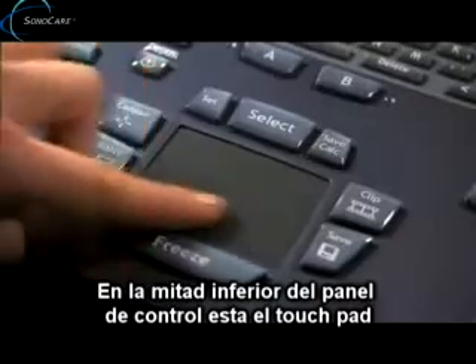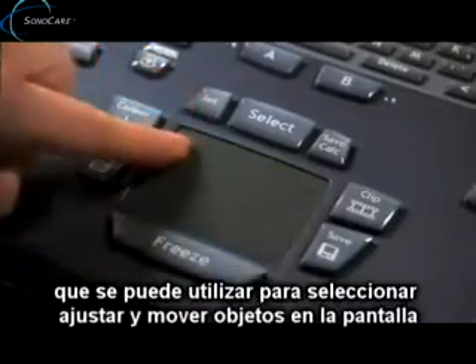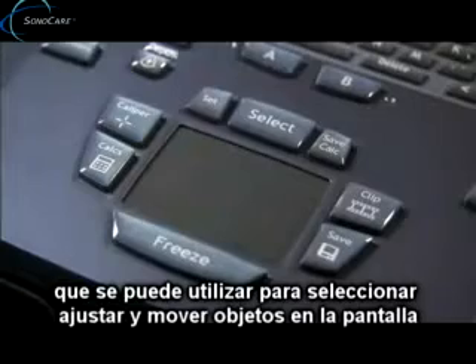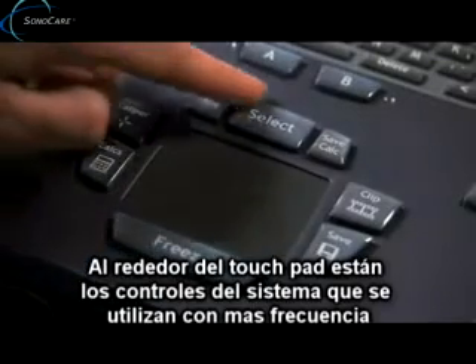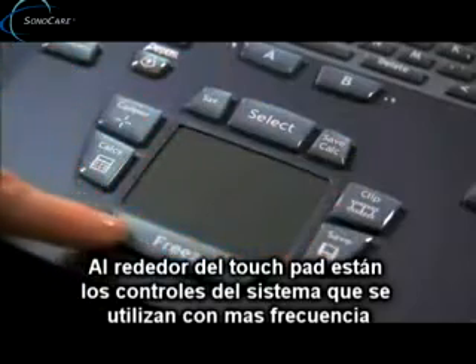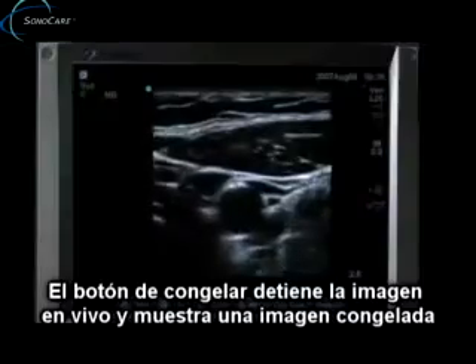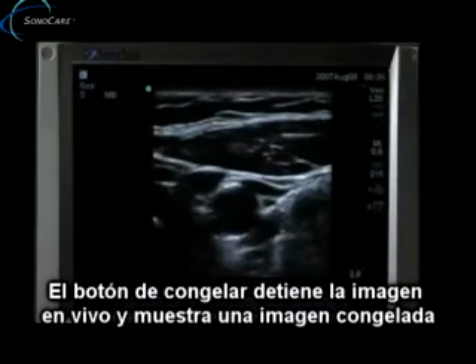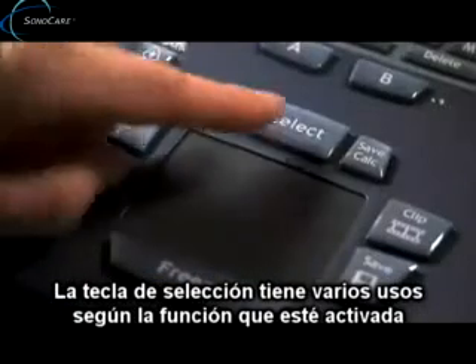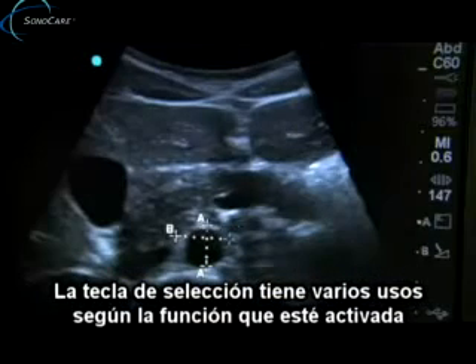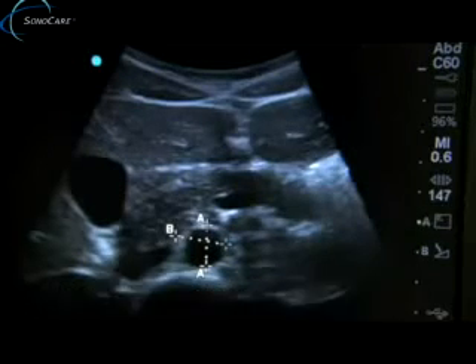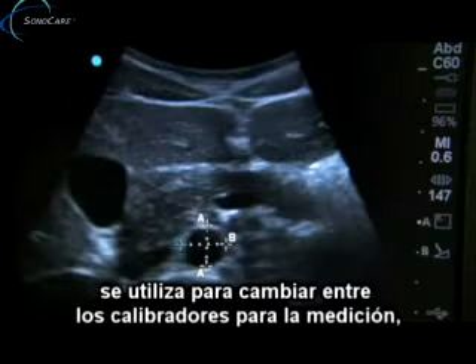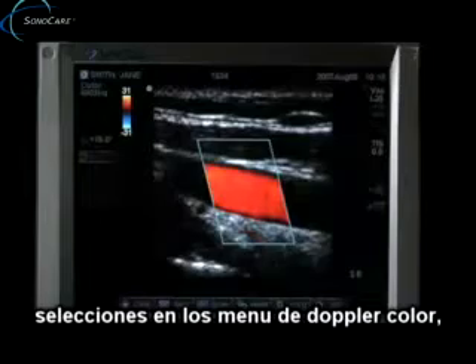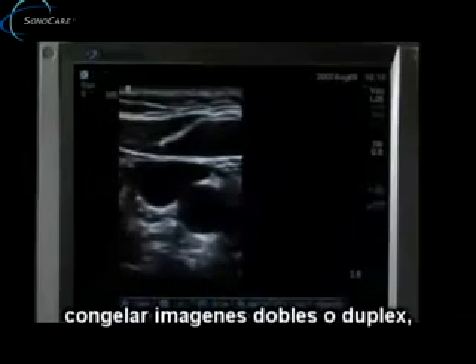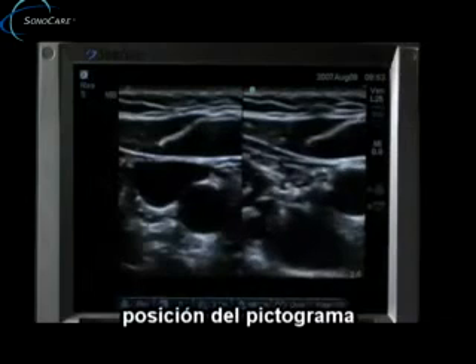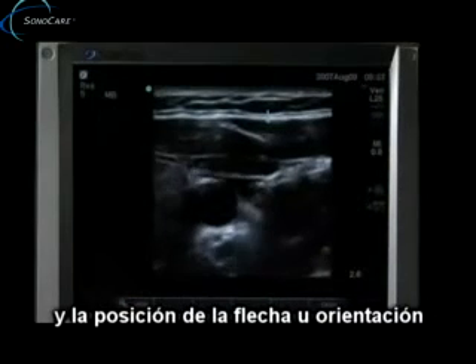In the lower middle of the control panel is the touchpad, which can be used to select, adjust, and move objects on the screen. Surrounding the touchpad are the system controls that are used most frequently. The freeze button stops the live imaging and displays a frozen image. The select key is used to make various choices depending upon the function that is activated. It is used to switch between calipers for measurement, selections on color and Doppler menus, frozen images in duplex and dual screens, pictograph marker position, and arrow position or orientation.